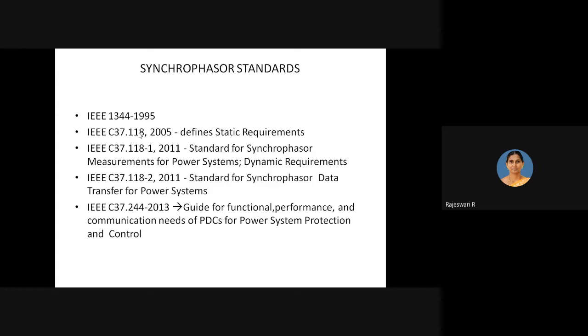And IEEE standard 1344, delivered in 1995, and this one, these two did not specify the requirement for the response of PMU to power system transients. So these two standards played an important role in steady state characterization of phasor measurement, not focusing on the transients. So IEEE approached IEC, resulting in a joint task, and they split this standard into two, that is C37.118.1 and C37.118.2, delivered in the year 2011.